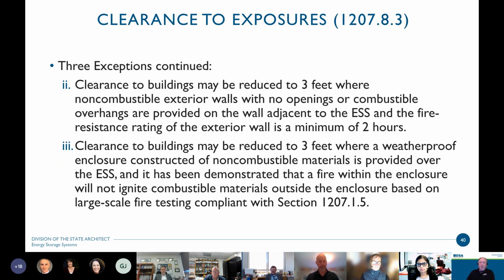And then exception 3 allows, again, down to 3 feet, where you construct a weatherproof enclosure of non-combustible materials, which covers the ESS, and it can be demonstrated that a fire within the enclosure will not ignite any combustible materials outside the enclosure based on large-scale fire testing. I don't see exception number 3 being used that much because of the cost involved with submitting this to UL for a UL 9540A test, a large-scale fire test. So I think we'll be ending up more in the exception 1 and 2 range.